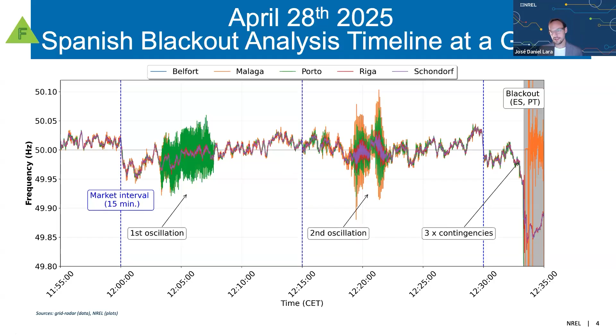If we take a look at the voltage measurements for the same period, we can see a measurement of the first oscillation going on, which mostly affected Iberia locally. You can see a measurement of voltage around Milan, where these oscillations did not actually make it through on the voltage across continental Europe. We can see the big oscillation that happened first in terms of magnitude, and a smaller one in terms of magnitude and voltage. So basically the conversation today is about how this came to happen, and what we can learn from this event about power system operations with large penetrations of inverter-based generation.